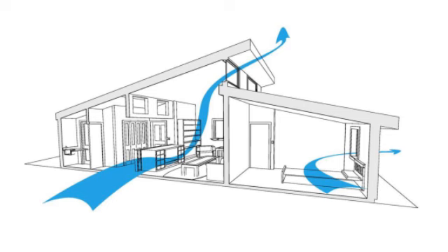The 1989 ASHRAE standard, Standard 62-89, states that appropriate ventilation guidelines are 20 CFM, 9.2 liters/s, per person in an office building, and 15 CFM, 7.1 liters/s, per person for schools, while the 2004 Standard 62.1-2004 has lower recommendations again.